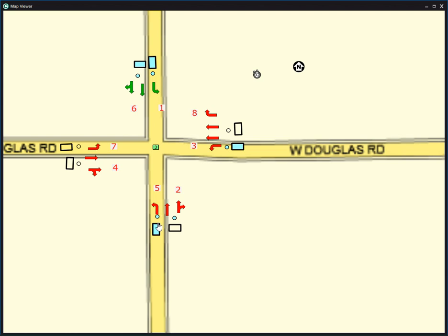Right? Nobody was in phase 5, or lane here, that northbound left, which is phase 5, early enough to trigger it. So it started off on the southbound lanes first. And now 2 will come up now that 1 is terminated. And there we go through there. And you can see every time this blue light turns on, another car gets detected in that location through there.